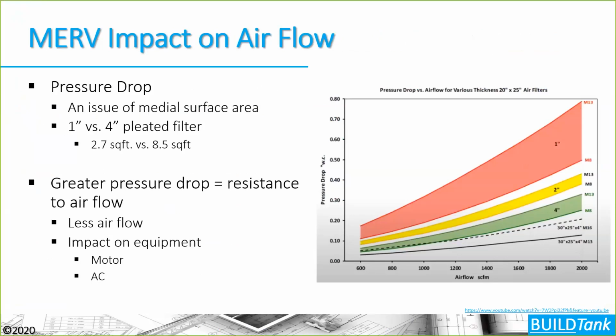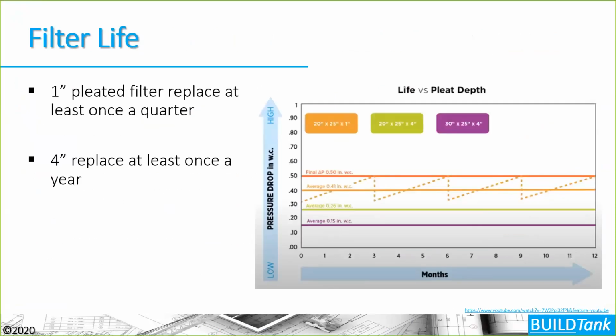Again, that pressure drop equals the resistance to the flow of air across the filter, which can have some negative impacts on whatever type of airflow system you're filtering. Also, 1-inch filters need to be replaced more often than 4-inch filters, so that's another reason to consider a better quality, bigger filter in your systems.